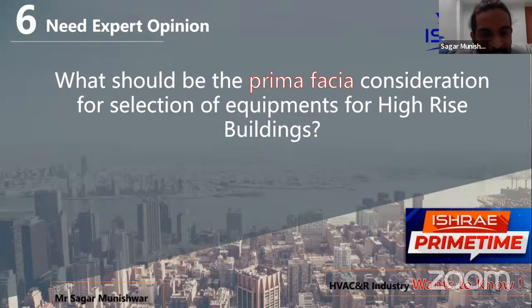Okay, I'll take Mr. Kedar Patki's question first, since it's registered in my mind. The answer is yes and no both. When we talk about the firefighting system, it's from two aspects. One is whether the local fire department is capable of handling high-rise buildings. There are a few states, a few cities which have a ladder which can go only up to 70 meters. The part I come from, say Thane, earlier did not allow any buildings of more than 70 meters because they had ladders up to 70 meters. So irrespective of whether my firefighting system is capable or not, they did not have the means to take care of it. To answer the question from a mechanical aspect, yes, we have firefighting systems capable of handling high-rise.